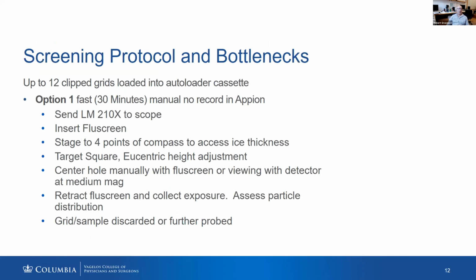The screening bottlenecks. We have two types of options for screening grids. You can put up to 12 grids into the microscope, but we generally use 4-hour sessions, so you've got to be quick with the screening. One is more of a manual operation. We essentially put the grid in, send a low mag image to the scope, put down the fluorescent screen, and go to the 4 points of the compass to look at what the ice thickness looks like.